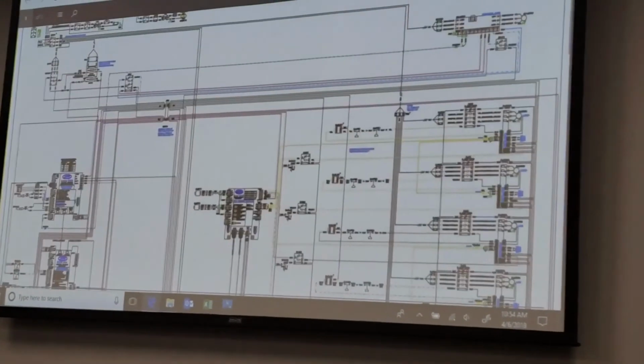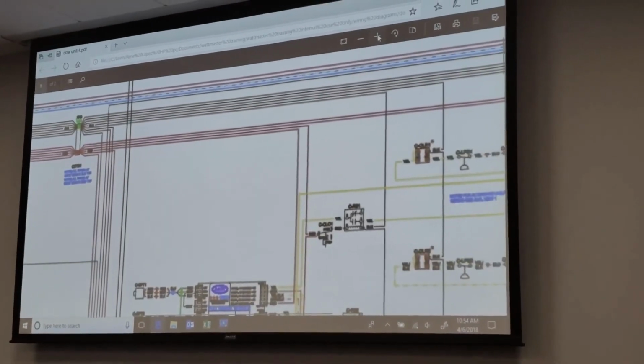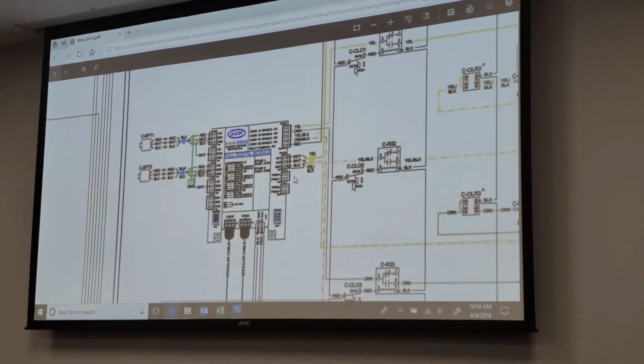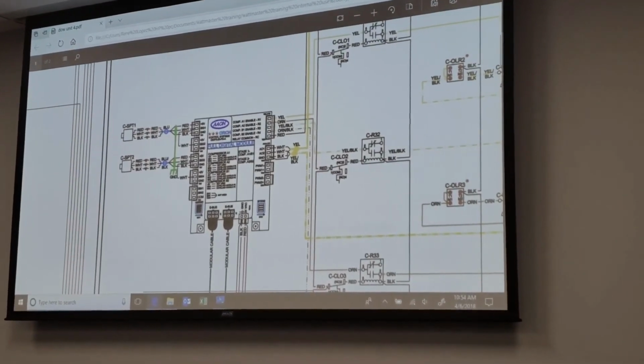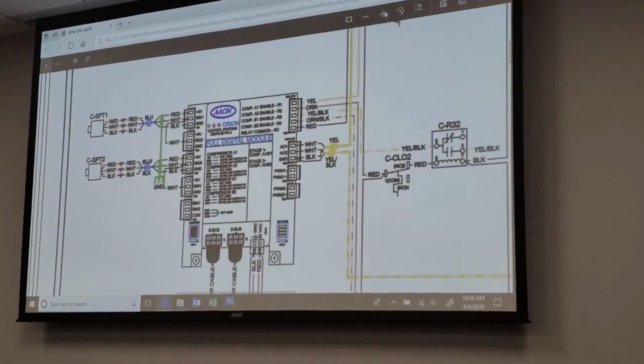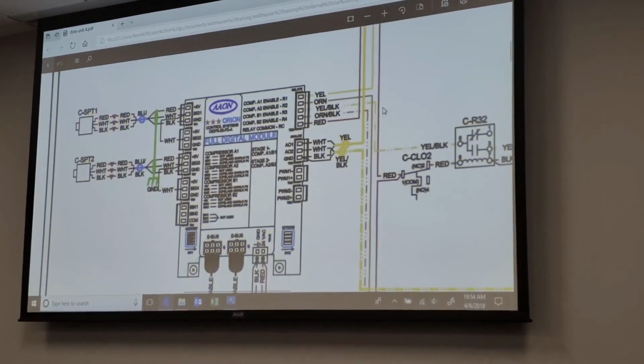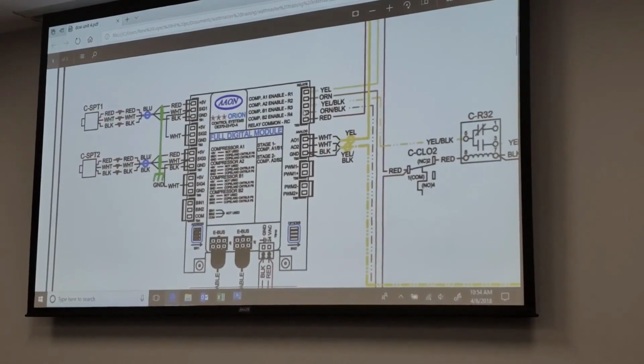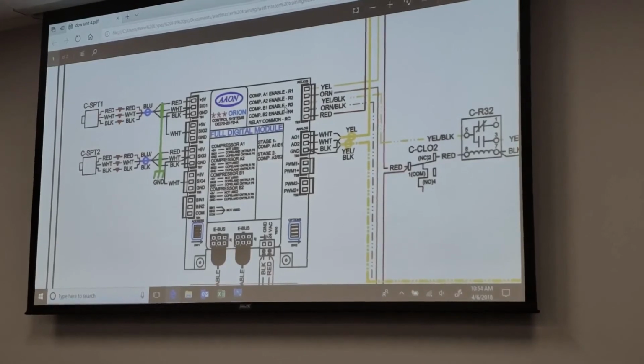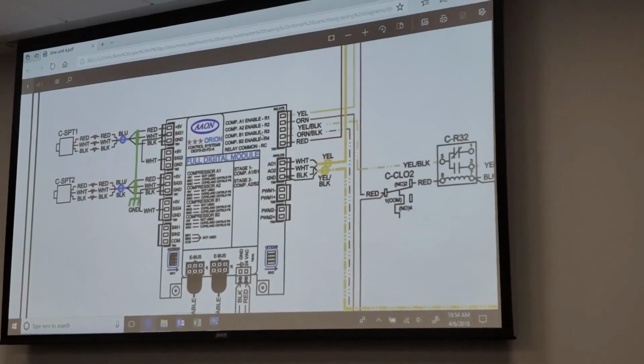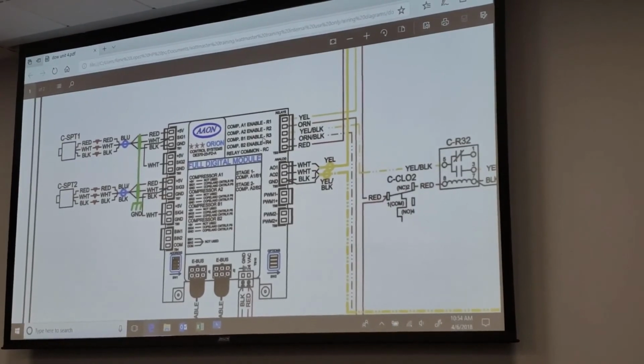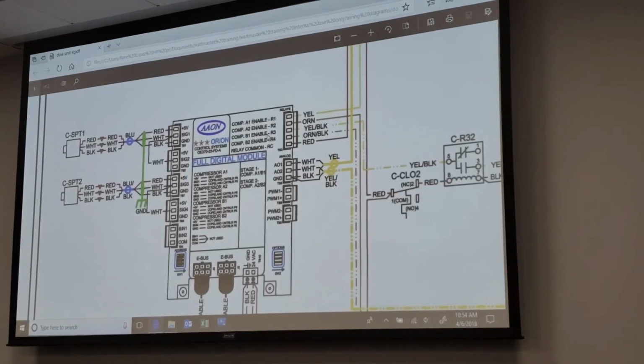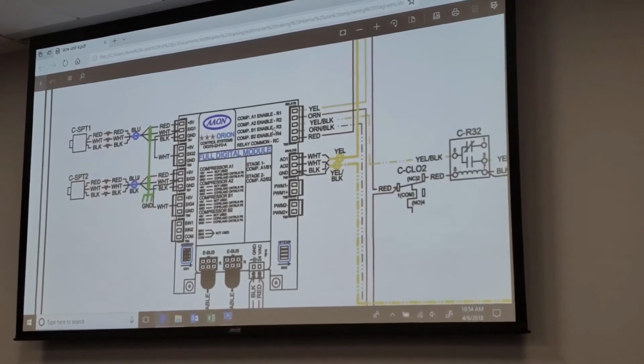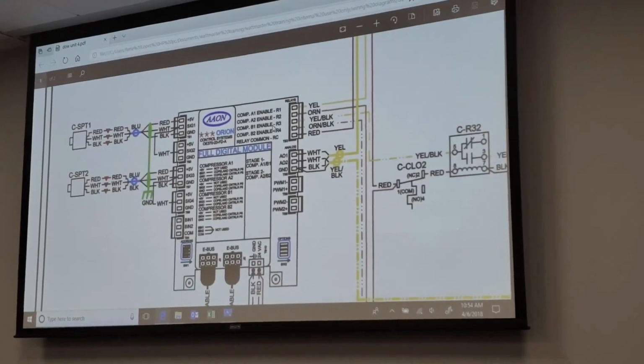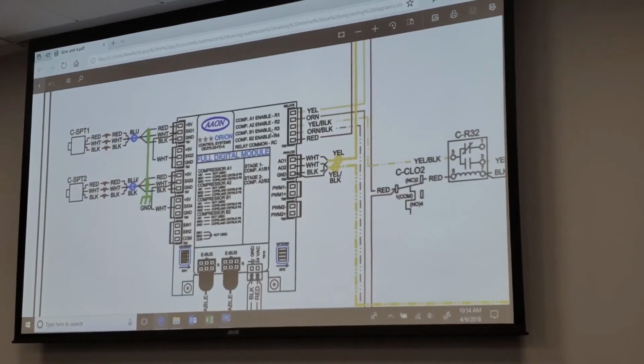Here's one out of Dow Chemical. This one here, I think it was a full digital module. I don't remember how old this drawing is. The older full digital modules would bring on relay 1, relay 3, which was compressor A1, B1, and then they would bring on A2, B2. That was the way they were staged. The new full digital module, about 4 years ago, they changed the sequence, and now they bring on compressor A1 and A2 together, B1 and B2 together.